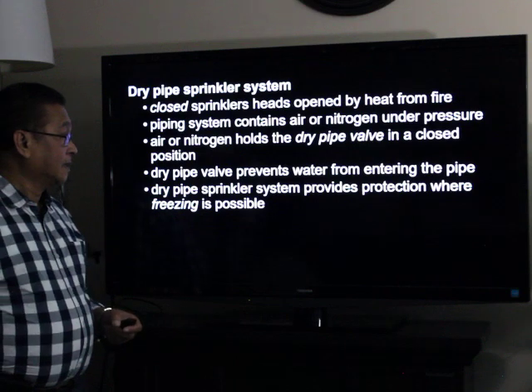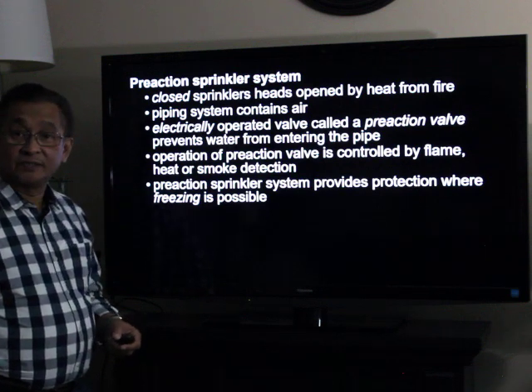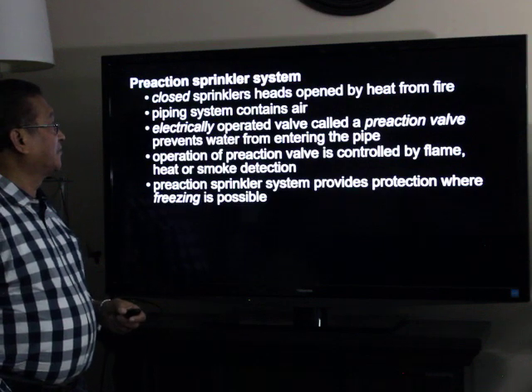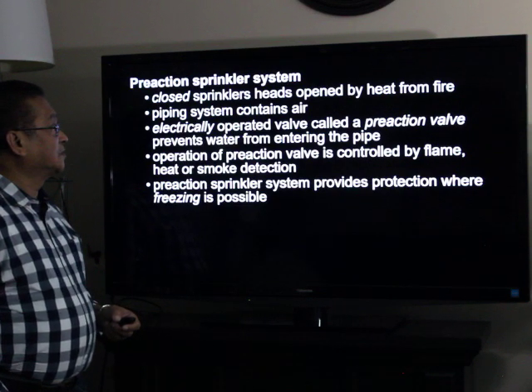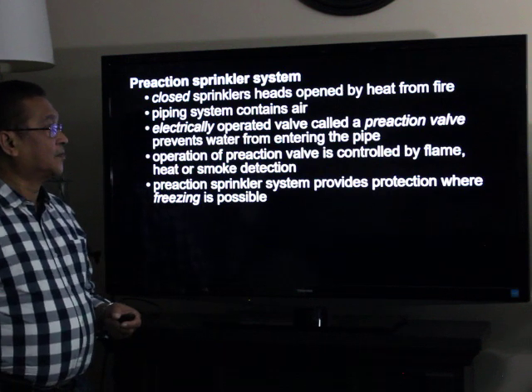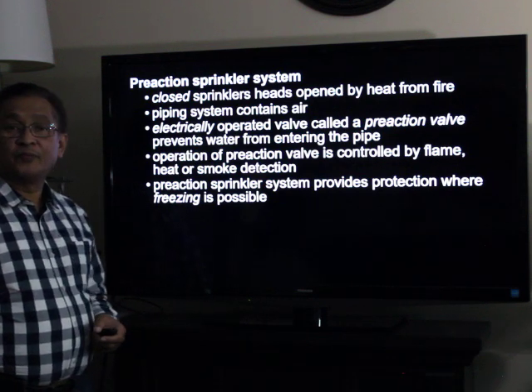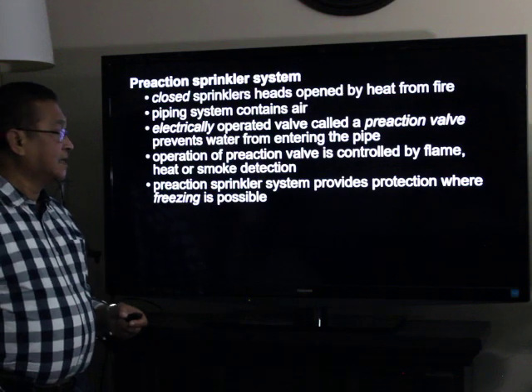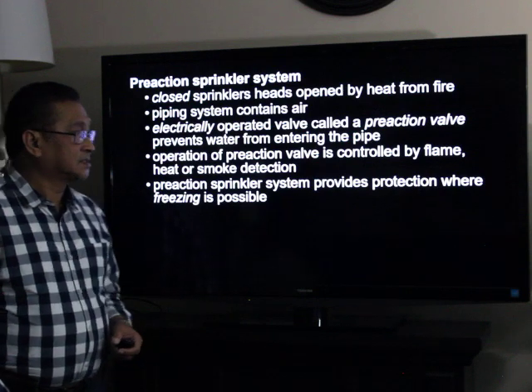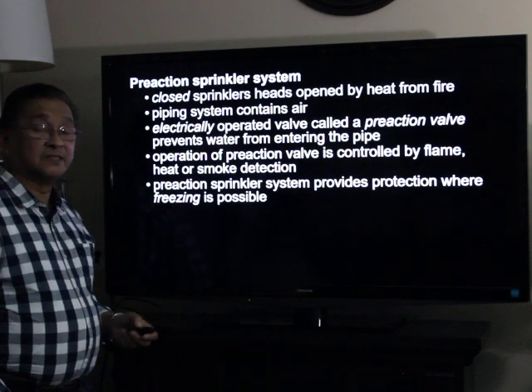The dry pipe sprinkler system provides protection in areas where freezing is possible. Pre-action sprinkler systems have closed sprinkler heads opened by heat from the fire. The pipe system contains air. An electrically operated valve called the pre-action valve prevents water from entering the pipe. Operation of the pre-action valve is controlled by flame, heat, or smoke detection. Pre-action sprinkler systems also provide protection where freezing is possible.